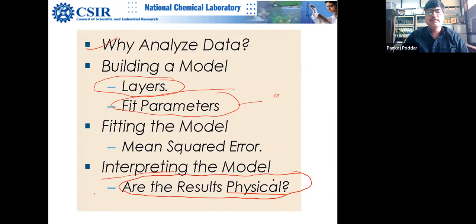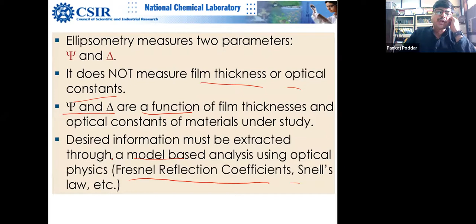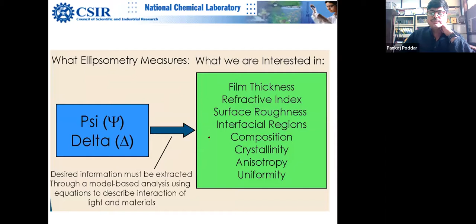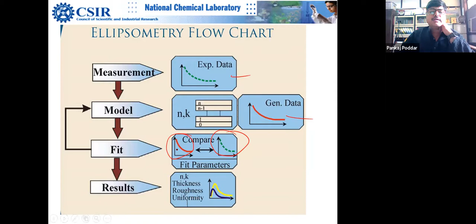So just to recap, we do not directly measure film thickness and optical constants. Of course, psi and delta are a function of these parameters, and we need to build a model, and then we use Fresnel's reflection coefficients and Snell's law, which are standard equations, to calculate and then find these values. How do we do that? For example, this is the flow chart: you do the measurements and you get some values, and then you make the model for n number of films. Then you generate the data, compare this versus this, and do least squares. This is an iterative process, so you do it over and over again until you have the right values of thickness, roughness, uniformity, and n and k, all kinds of things.